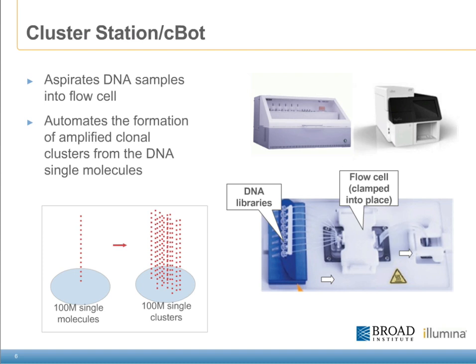Either system contains similar fluidics, similar thermal station to regulate temperature, and similar housings to hold your DNA libraries and put your specific DNA and primers onto the instrumentation. In the image at the bottom, you can see the DNA libraries in strip tubes on the left-hand side being aspirated through a manifold where the flow cell is clamped into place on top of the thermal station, hybridizing the DNA to the flow cell at the start of the cluster process.